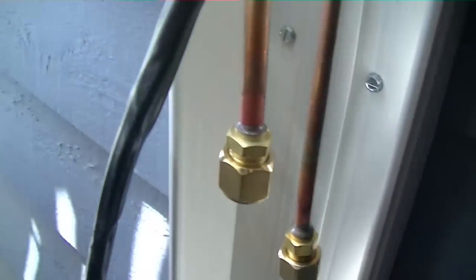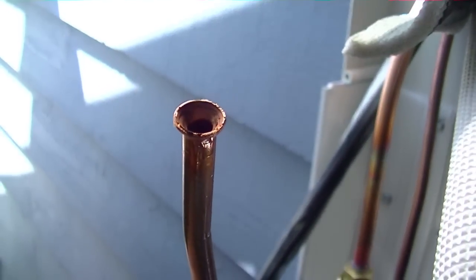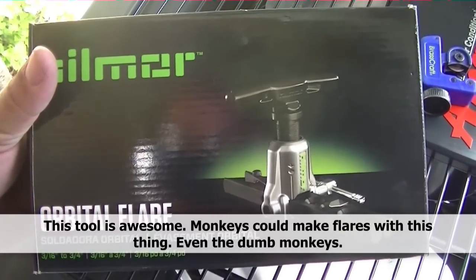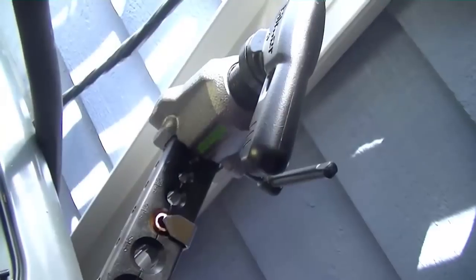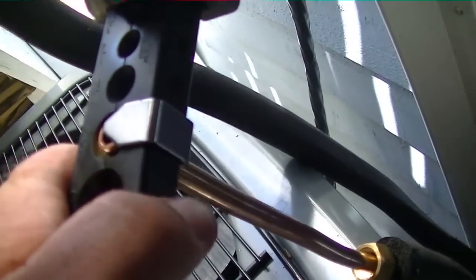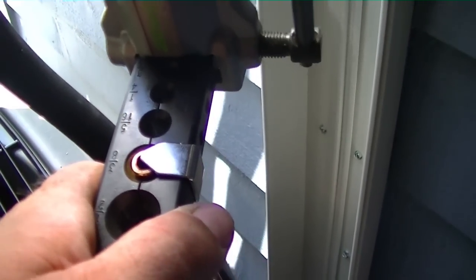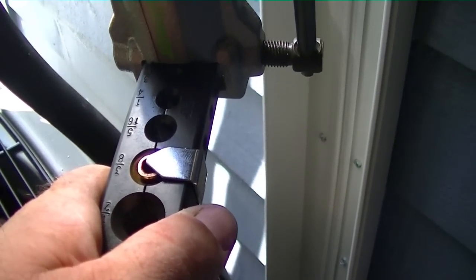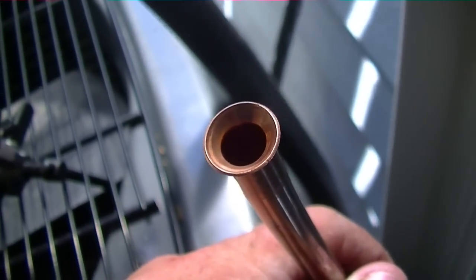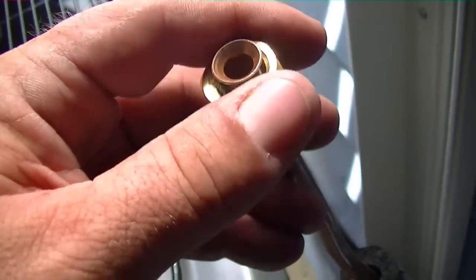We have our line set coming out of the wall. I'm going to take the nuts off — we have our flare nuts and flares on the existing line set since they come with flares, but we're going to cut those off and make our own. We have the new hilmor orbital flaring tool. It has a little automatic stop so you don't go too far — you slide the tool over, there's a little notch, you just crank the flare down and when you reach a certain point it won't let you crank any harder; it has a little clutch so you can't over-tighten. Here's the flare the hilmor tool made — very nice, very pretty.